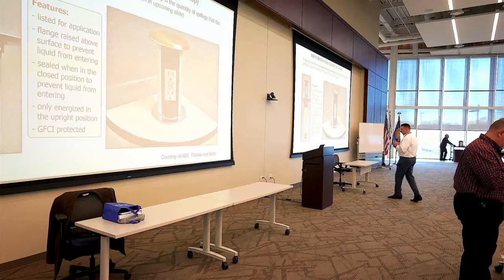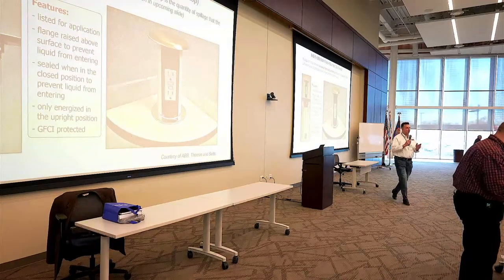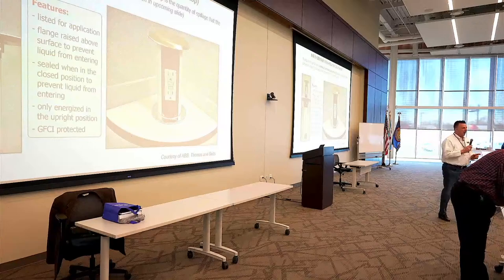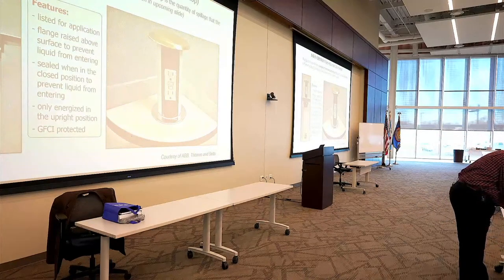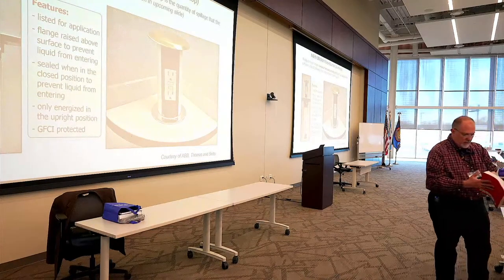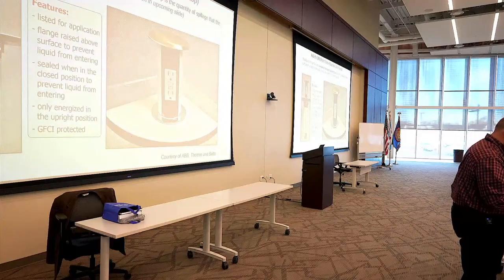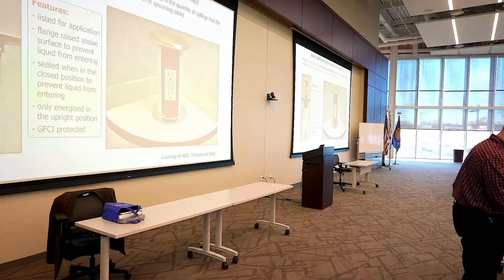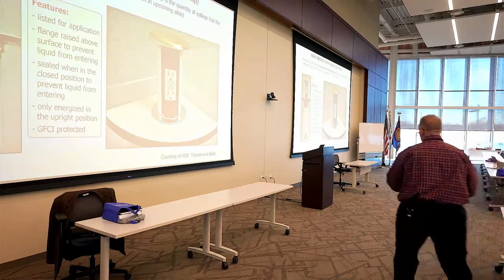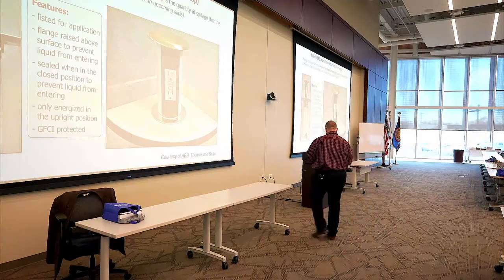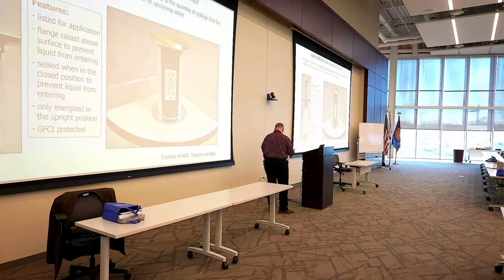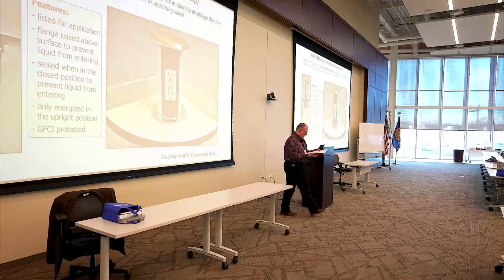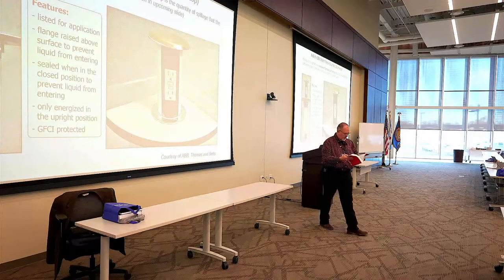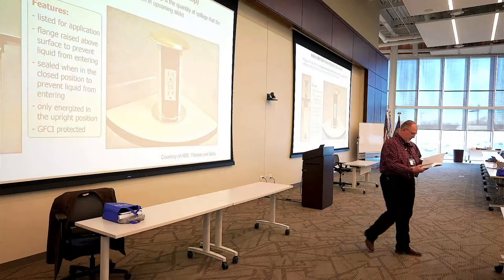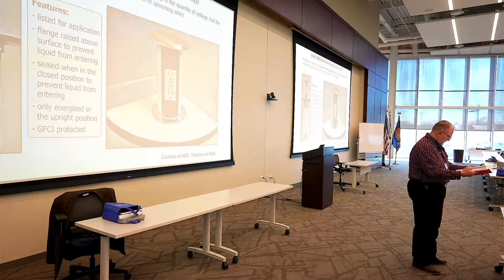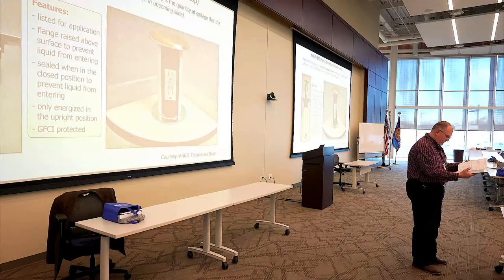Yeah, this is a great one, especially with the listing being different about work surface and countertop, right? We'll go through a couple slides where you could have a listed device that's listed for countertops, because what we used to go by was the amount of spillage. It's okay for a countertop, it's also okay for a work surface. We'll have a receptacle, the pop-up type that we'll show you. We'll have one that's listed for a work surface because it was tested to a lesser amount of liquid, 8 ounces. You couldn't use a work surface receptacle in a countertop.